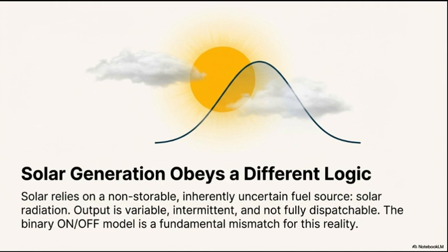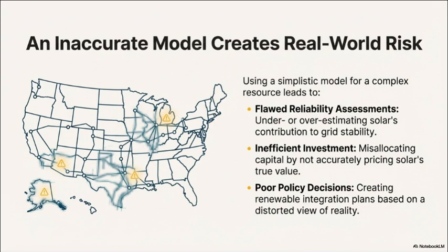That makes perfect sense. Once you have that ELDC, you can run the full spectrum of quantitative metrics, which the paper calculates over a standard one-year horizon. Let's quickly define those three critical categories, starting with reliability. Okay, reliability is quantified using two key metrics. First, LOLE, or loss of load expectation, measured in hours per year. It tells you the expected duration of time the system will be short on supply. Hours per year. Okay. Second, EENS, which is expected energy not served, measured in megawatt hours per year. That represents the actual volume of energy shortage.